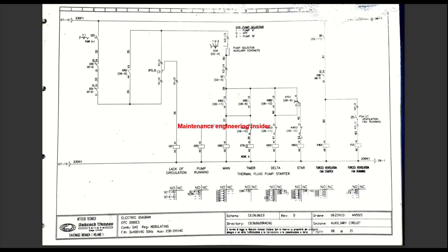Also make sure KM2 is not energized at the same time, because if KM2 is on, this contact will remain open. KM2 is the delta starter — star and delta can never both be energized at the same time; that is the essence of this interlock. We also know this cable comes from the neutral on page 7, section 15, and it continues to page 9, section 1.